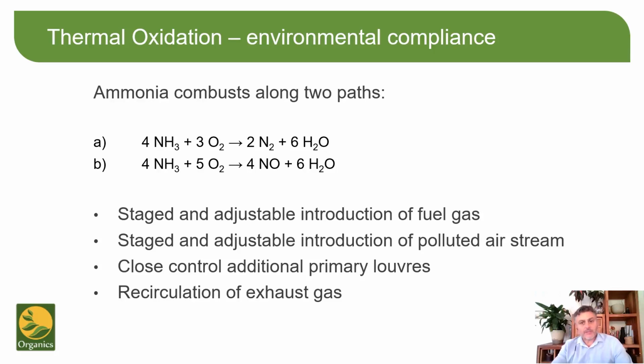Ammonia has 2 combustion possibilities. One produces nitrogen and water, and the other produces the pollutant nitric oxide. Equation B here should only happen in the presence of certain catalysts, but experience has shown that even if a small amount of the ammonia follows this path, then the emissions test will be failed. Emissions limits for NOx are typically around 150 milligrams per normal cubic meter at a 3% oxygen reference, so very tight. Along with NOx, other species being monitored are usually ammonia, methane, carbon monoxide, oxygen, SOx, and so on.